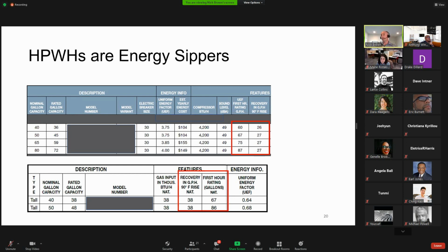If you're designing the building from scratch, put those heat pump water heater closets off the corridors to house 2, 3, or 4 units in one closet. That way you can maintain them with less of a noise problem. The other option is the skid model - 8 or 10 tank heat pump water heaters providing hot water to 20 or 30 units, all ganged together. So the answer is yes, there are heat pump water heater solutions to electrify multifamily buildings.